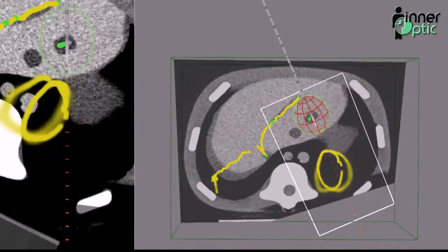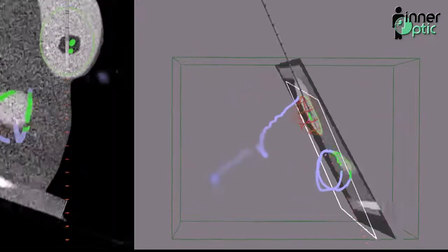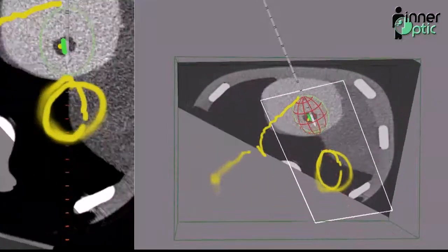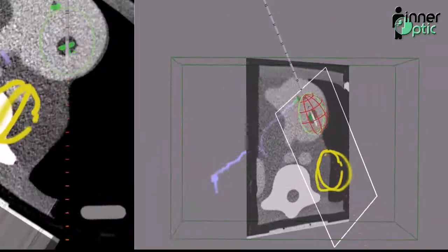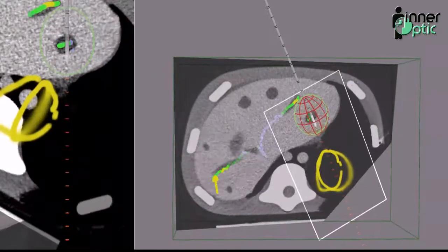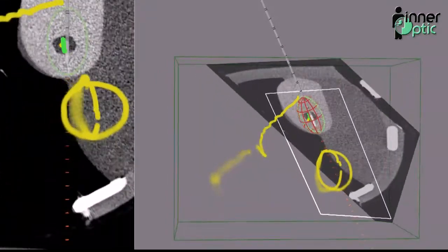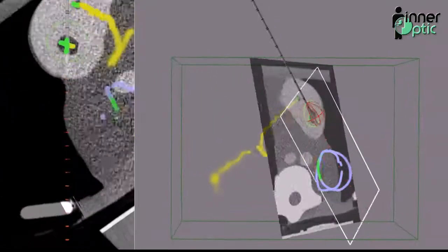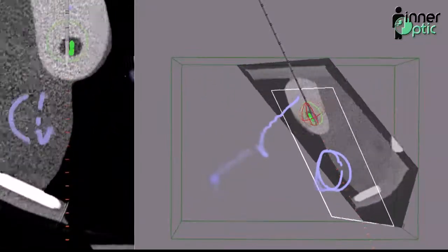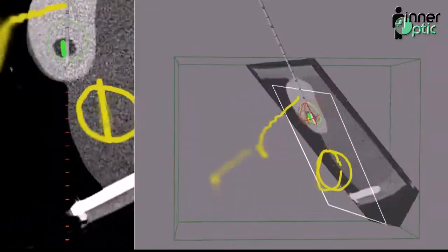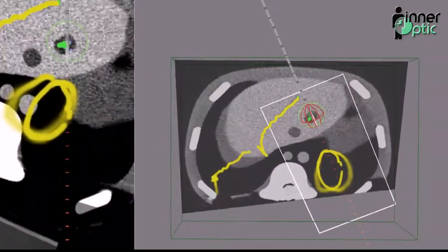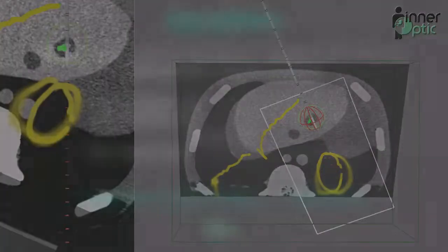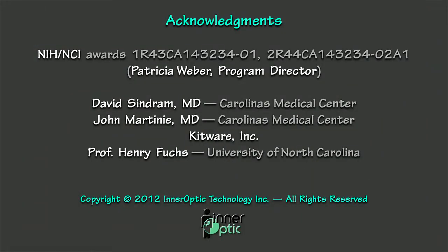and I can get an idea, by spinning the needle, of what tissue is inside the ablation zone. I can see I'm actually still very close to that blood vessel. So by reducing the power on the ablation generator, we can still have enough margin around the tumor while fully encompassing the phantom's tumor.